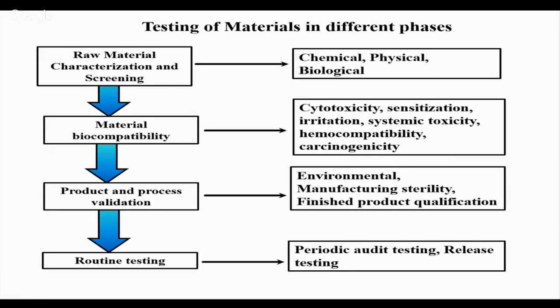Similarly, the chemicals composed of the specific material: if exposed to body fluid, will they have any undesirable consequence? Similarly, also the biological response. So we need to do the chemical testing, the physical, physico-mechanical testing, and also the biological testing.